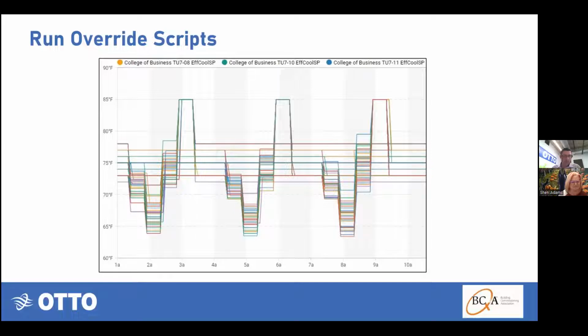What you're seeing here is an example of 3 batches of testing we ran at a particular higher ed project, where normally we only run 1/3 of the terminal units at a time, to create more reasonable conditions for the parent equipment: the air handler, chill water, hot water plant. But if we know an application is supposed to handle 100% load and redundancy, we run 100% of the units all at once. That's totally flexible, but this shows 3 very deliberate, well organized, choreographed batches of testing on hundreds of terminal units.